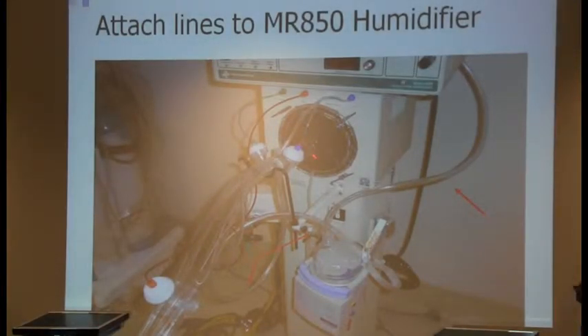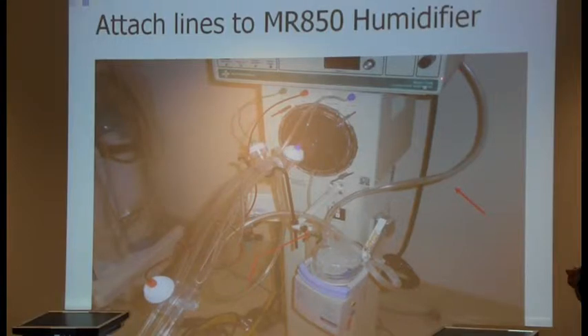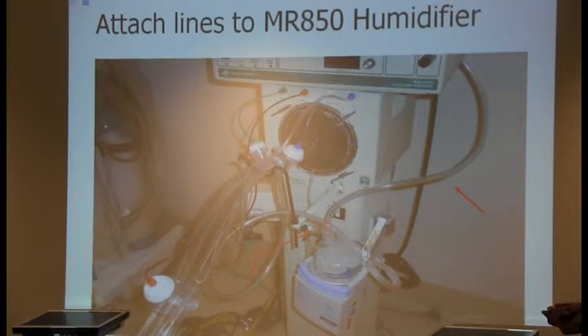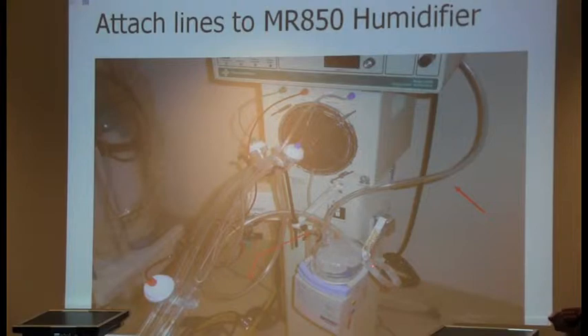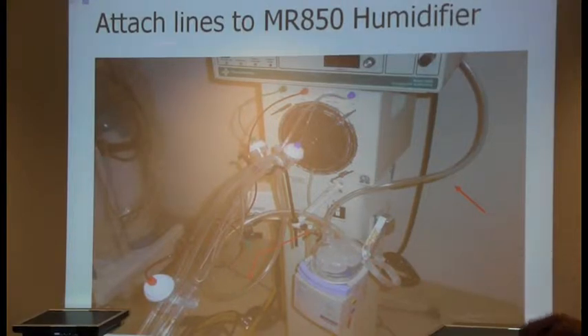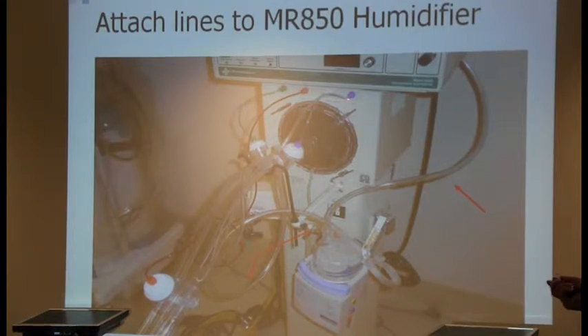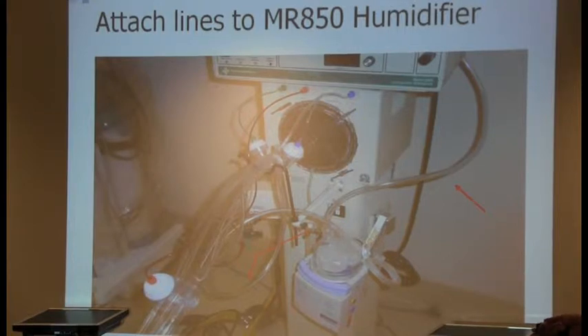All right, so once we have everything assembled, on the back is your bias flow gas. You have to hook it up and make sure it gets the inspiratory limb, goes over the humidifier, gets moisture, and then it goes up through here to the patient and cycles through. So here's your green line to your mushroom cap, blue line, here's your red line, and here's your white pressure line. Make sure everything's connected.